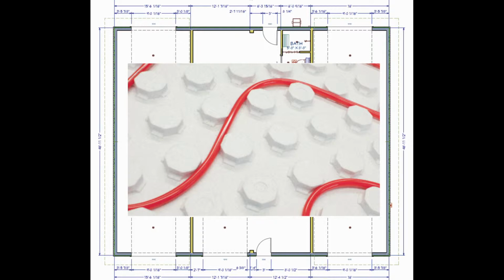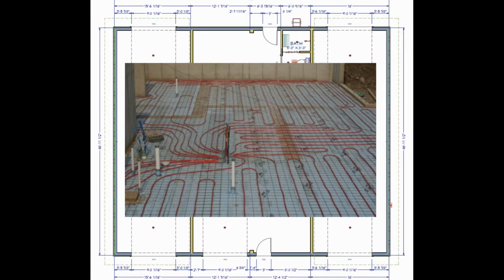I plan on putting in a 5-inch slab instead of a 4-inch slab, so that heat's going to have a long way to go—even a 4-inch slab is a long way for the heat. I'd rather have it 2 inches from the top of the slab instead of 4 inches, or in my case 5 inches.